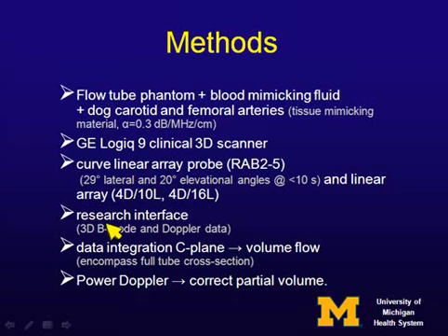And then we had a research interface where we actually took the Doppler data and did this sum to calculate the flux. However, like I said, this is conceptually quite simple and could easily be done on the machine. The integration calculates the flux, as I said, and that gives you volume flow. There's some partial volume issues which I'm not going to get into, and we use power Doppler to correct those.